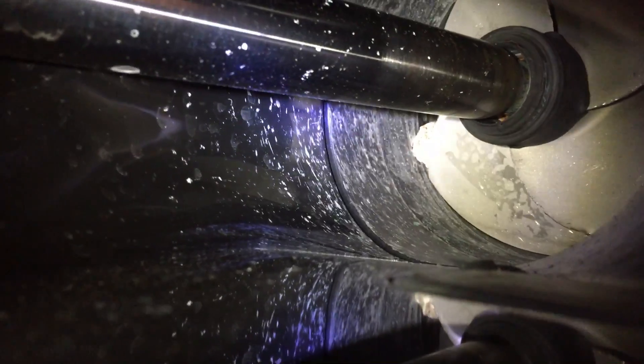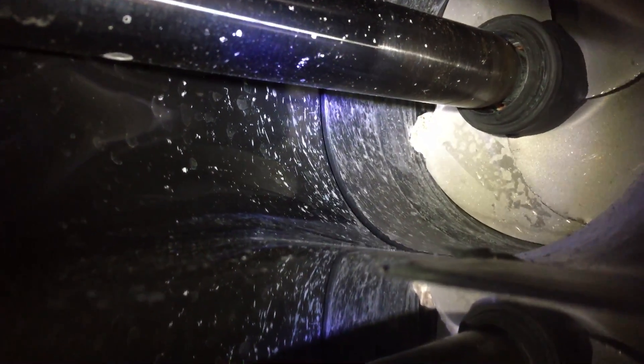Come under here — as you can see, the impeller is completely destroyed. There's nothing left, and if I can get the light just right, see right there at the top — there's a rock wedged in there. And what that has done is it has actually locked this up.